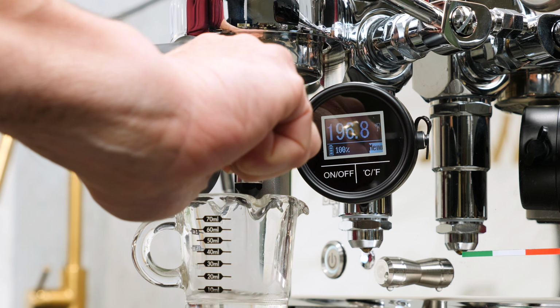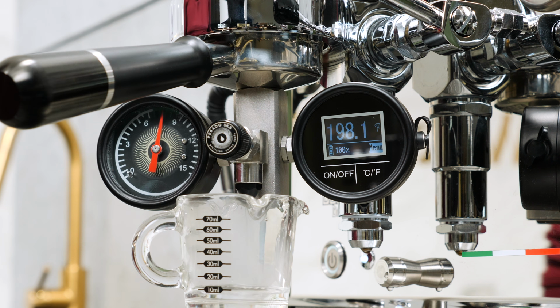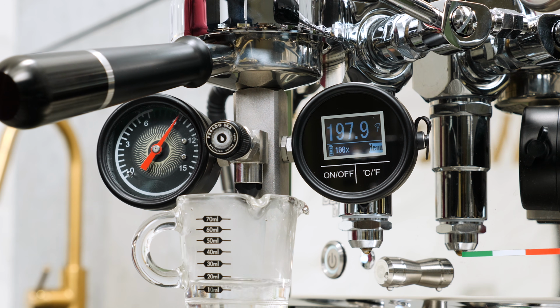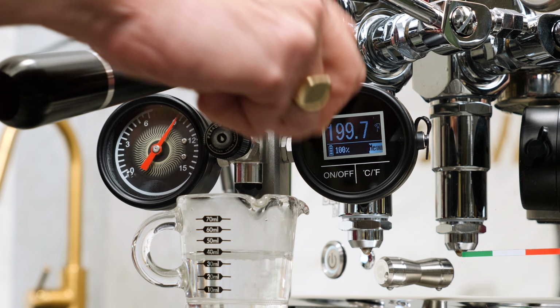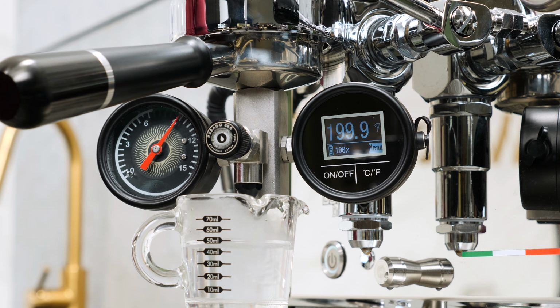I disregard the first 10 seconds as brew pressure comes up to 9 bar and temps equalize in the test device. At 10 seconds in, we're at 198.1, rising to 199.9 at 16 seconds, with that temp holding until 23 seconds and falling slightly to finish at 199.4 at 25 seconds.